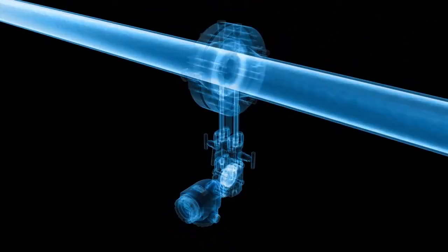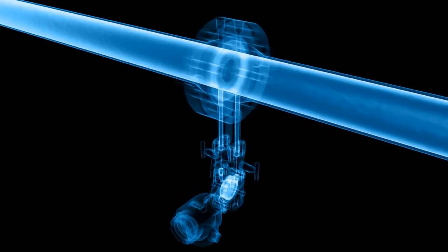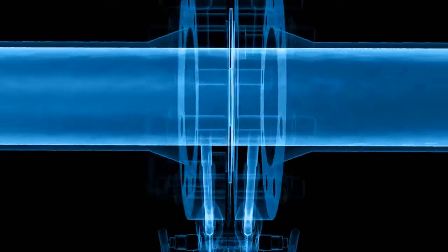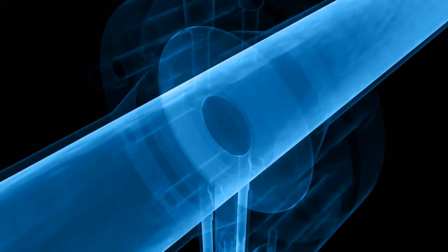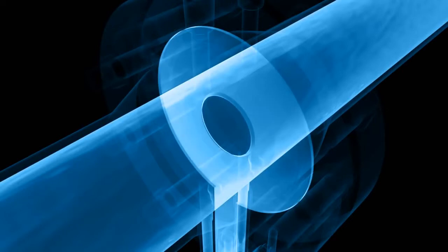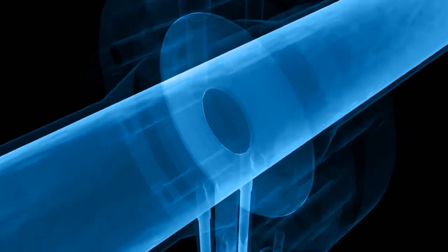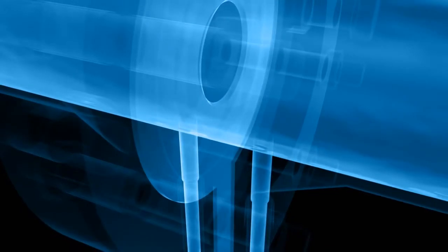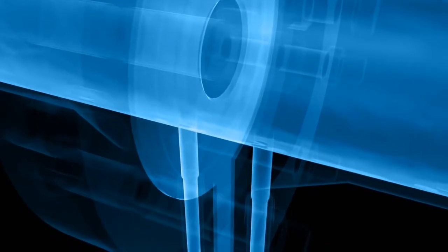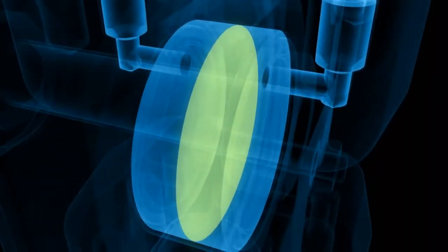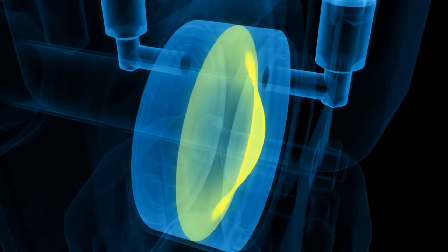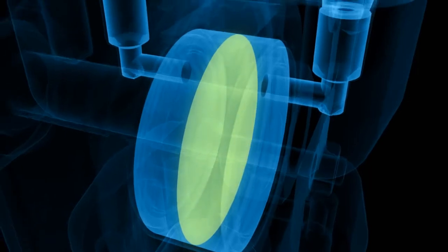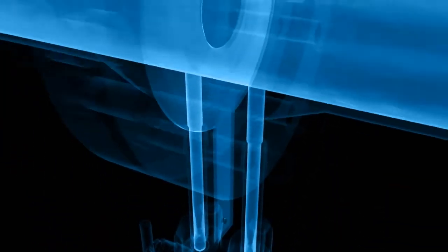Here is how this measurement method works. Differential pressure flow meters have an artificial restriction integrated into the measuring tube, illustrated here by the example of an orifice plate. Two holes are located in the pipe wall, one before and one after the orifice plate. Two separate tubes connect these holes to a differential pressure sensor, with its two pressure chambers separated by a diaphragm. The tiniest pressure differences in the flowing fluid can be precisely measured.